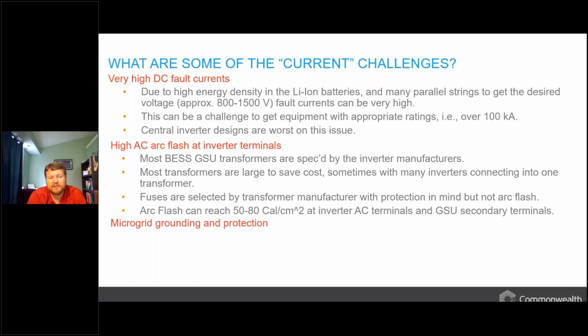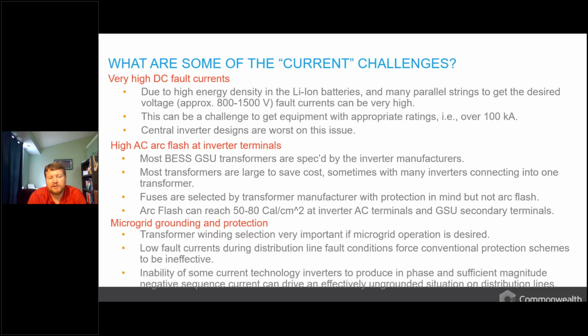Another challenge we're seeing on battery energy storage is dealing with microgrid grounding. When we use a battery energy storage system on a distribution system, we have the opportunity to form a microgrid. I'm going to define a microgrid as a separate grid from the typical utility connection. After we lose the utility connection, we're going to form our own grid with the battery and the inverters from the batteries themselves. When we do this, it provides some challenges. Normally we have a lot of system inertia and system strength, but when we're in this IBR-based microgrid, we lose a lot of that. So it can be very challenging sometimes to provide effective grounding and also protection settings that can detect and clear faults.